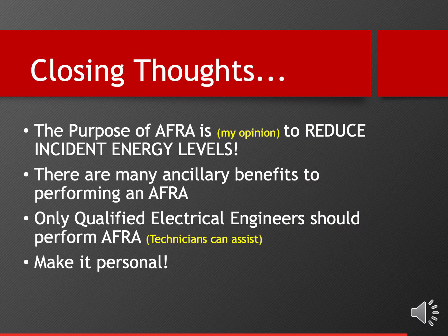So the closing thoughts. Well, the purpose of arc flash, in my opinion, is to reduce incident energy levels. You should be aware that the engineering calculation software and the engineering standards for this actually don't require us to lower incident energy. It really requires us only to create a label and properly label the system. So I think where we engineers get paid the big bucks is to lower incident energy if we can, and that's what I would recommend we do, but it's just my opinion.